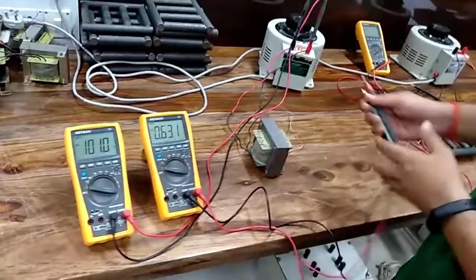Now we proceed to the testing of the transformer, specifically the secondary windings. What we have finally got is these two wires are the two ends of the strand from the first winding, and these two are the two strands of the other secondary winding. We have to ensure that the two ends of the same wire must not be shorted.